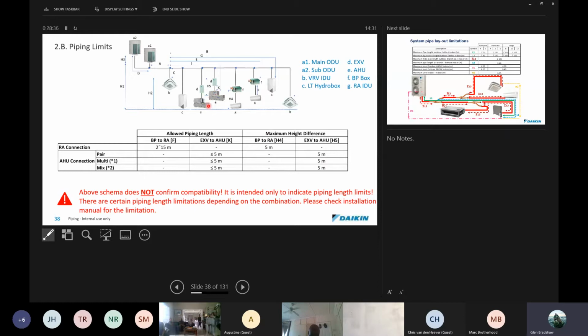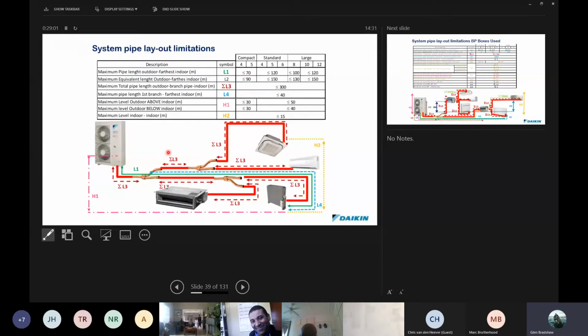So you cannot have 5 meters height and 5 meters of length. It's 5 meters combined. So you can either go up 2 and across 3, but never 5 and 5 and have 10 meters of piping. Okay, BP to RA boxes, that's this measurement over here, anywhere from 2 to 15 meters, but I'm going to give you a guideline for that as we build this up a bit further.